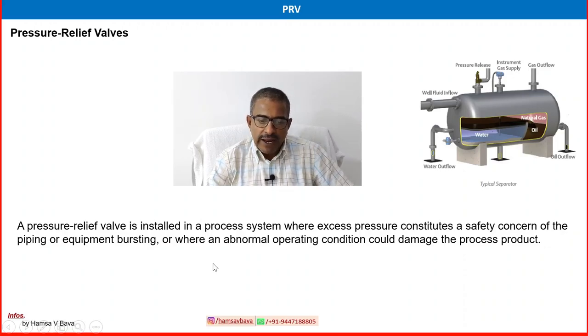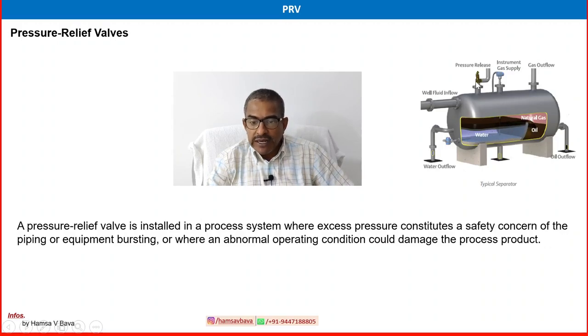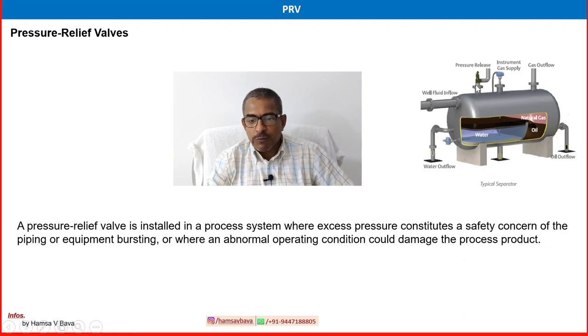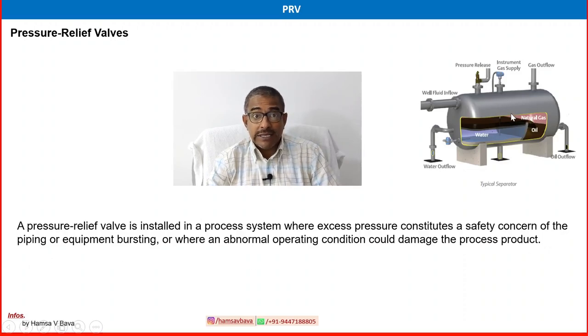A pressure relief valve is installed where excess pressure constitutes a safety concern of piping or equipment bursting, or where an abnormal operating condition could damage the process. For example, in a three-phase separator where wellhead fluid is processed into oil, gas, and water — the relief valve is connected to protect the separator from extra high pressure. Normally, the instrumentation system handles high pressure, but extra high pressure causing hazardous conditions is handled by the PRV.